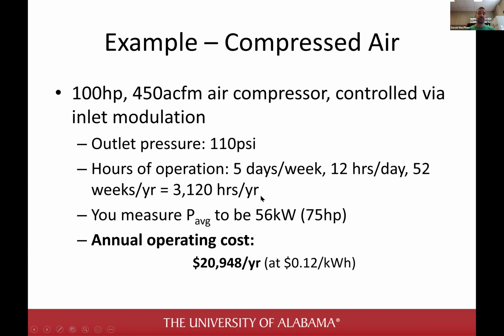I've seen them very close to 8760, which is the maximum amount, especially for those manufacturing facilities that are operating, I don't know, 18 hours a day, 6-7 days a week. Some of them are 24/7. So anyway, you've got this compressor. You go out, you measure the current, or you can measure the power directly. You're probably going to measure the current and calculate the power with that equation I had a couple of slides back. And you say, okay, well, it's drawing 56 kilowatts or 75 horsepower, which is about 75% on average.